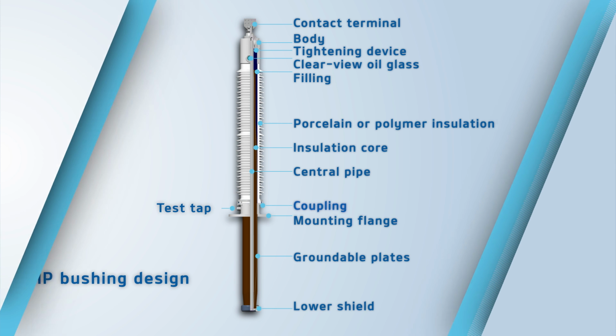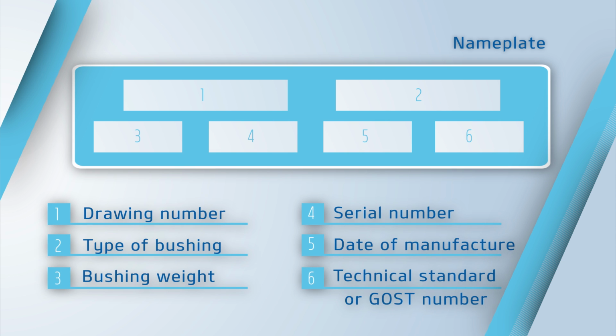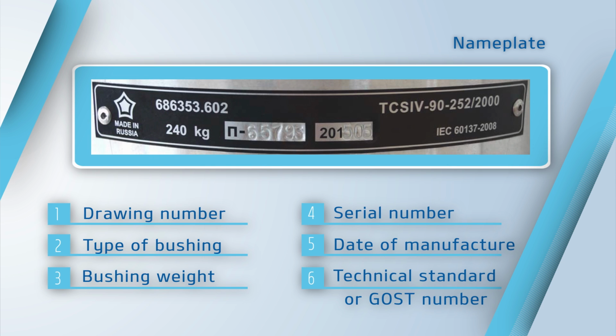There is a corrosion-proof nameplate on the coupling of the bushing. It contains maker's trademark, drawing number, type of bushing, bushing weight, serial number, date of manufacture, state technical standard number. Take a look at this nameplate example here. Mark that the unique serial number is fulfilled by impact. So with all other data possibly lost, one can easily restore all required information on the bushing, starting with the date of manufacture and ending with the acceptance tests results at the factory.